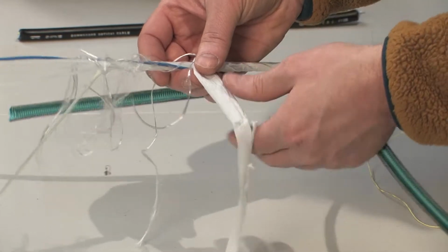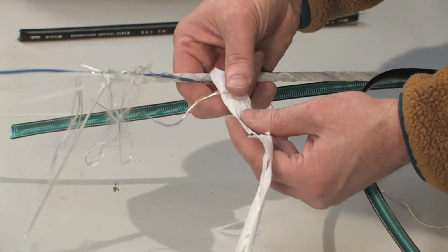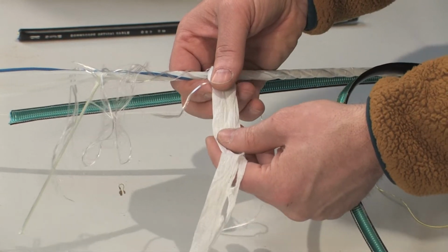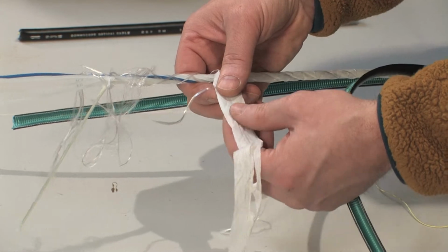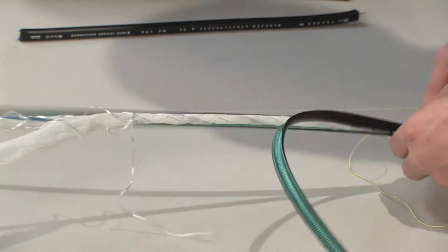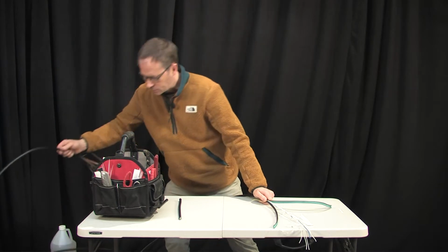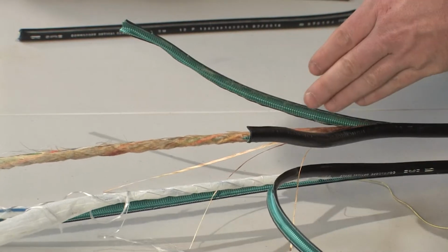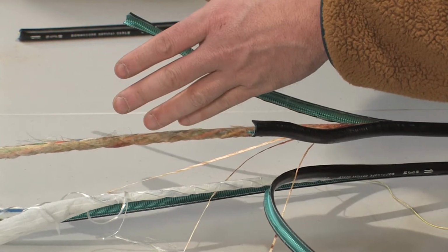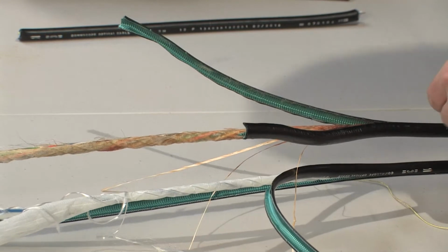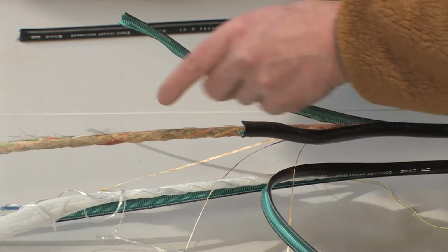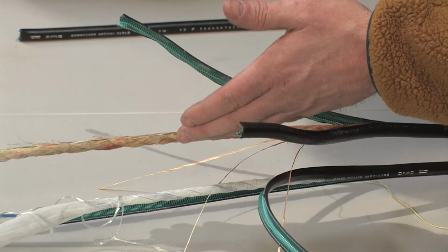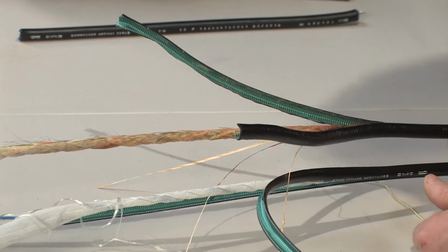You'll hear us refer to cables as being icky cables or gel-filled cables, and nowadays they don't put the gel inside the fiber itself, but they only put in this fabric. This fabric, once it gets wet, turns into the gel, and I have a piece of cable here to show you what it would look like if it was to get wet. As you see here, it's discolored, which usually just means that it drew some sort of water that had mud or something like that into the cable itself. But now this is tacky and it'll stay wet or feel wet. It won't dehydrate off. It'll stay wet like this for decades.